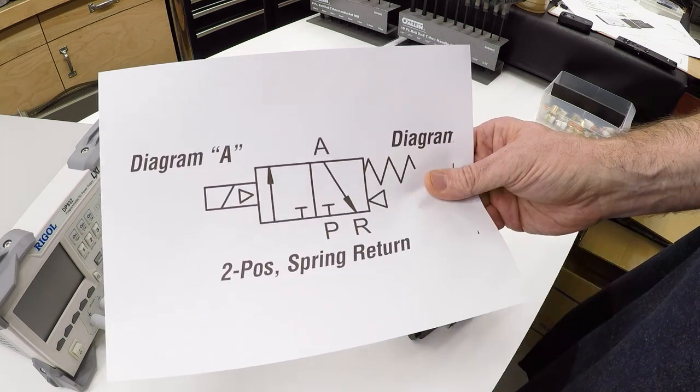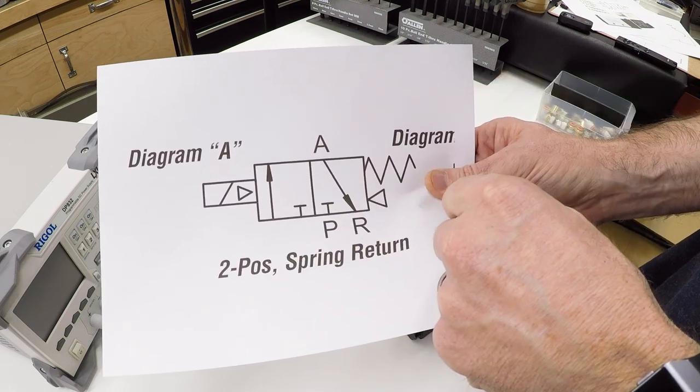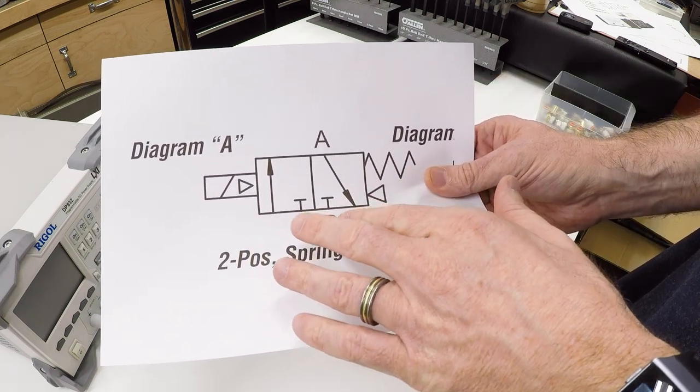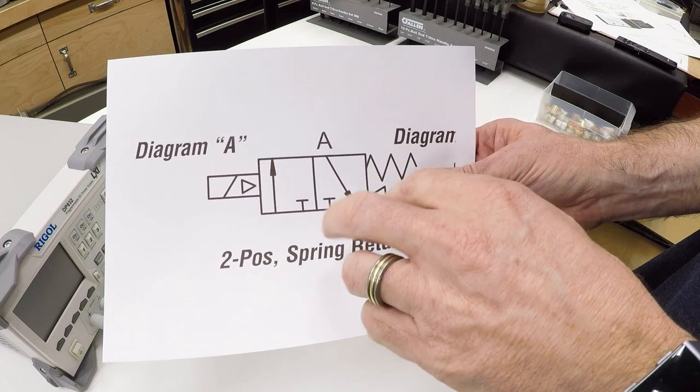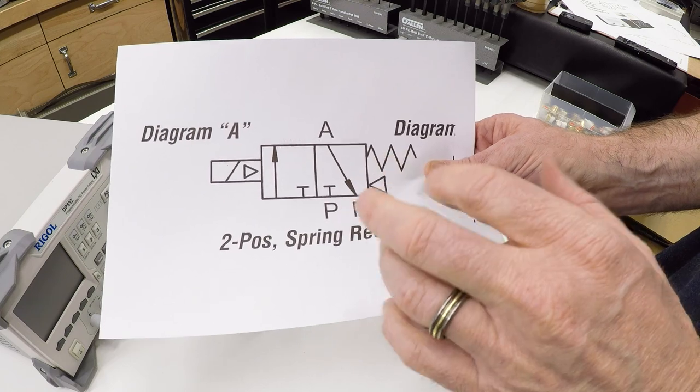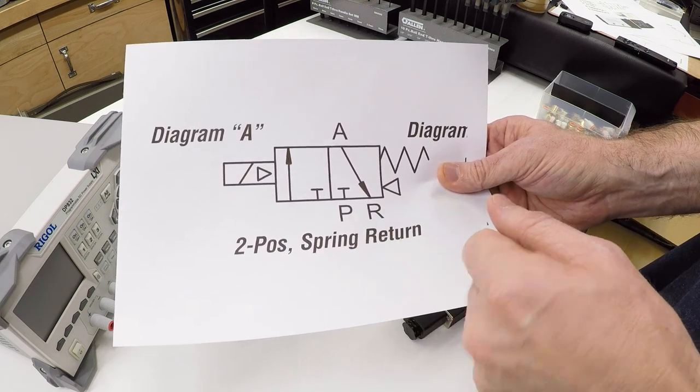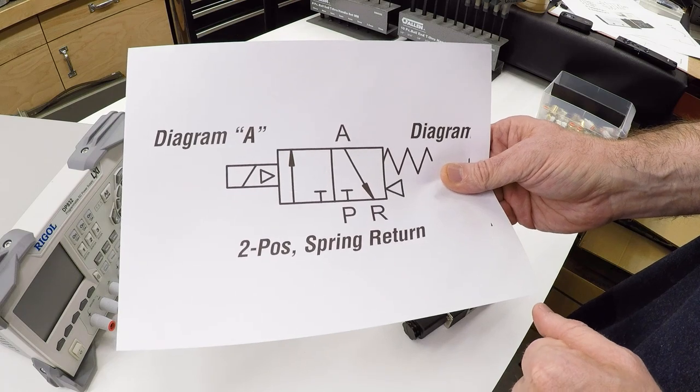These valves require less current generally on the electromagnet, and they also move more rapidly. Many of these valves are rated to switch at five hertz, like five times per second. They can change position. The valves can do that with the pilot assist.